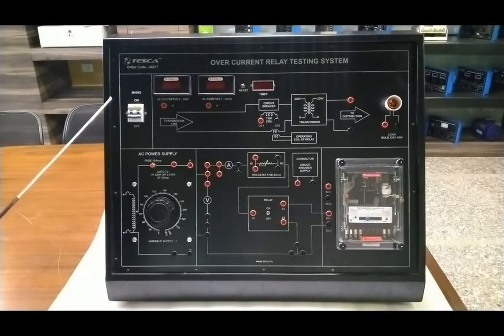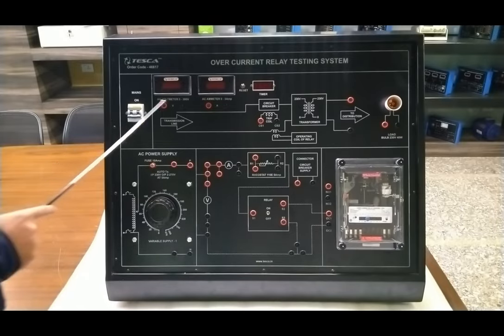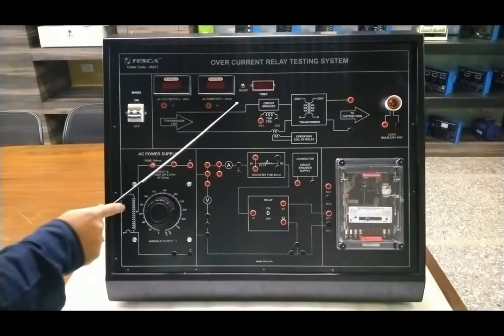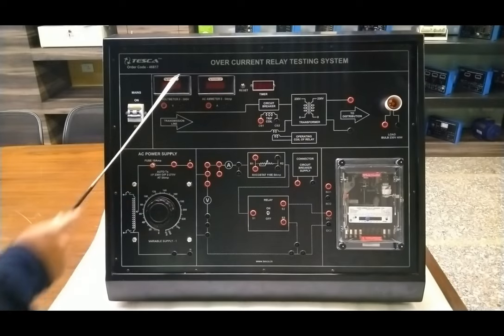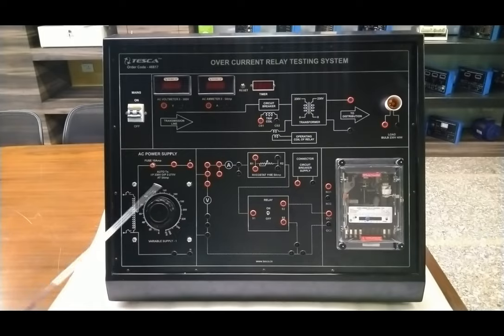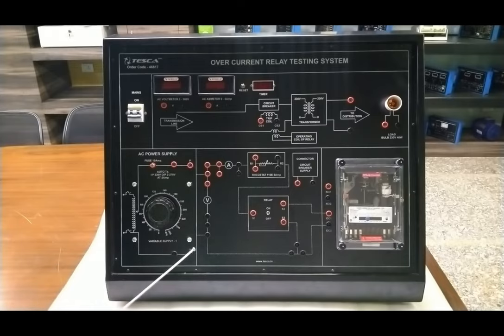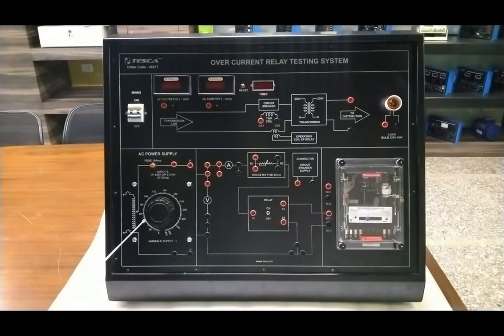You can turn the complete system on and off with the 230 volt power supply. As you turn on the system, the general auxiliary power supply to the meters and timer is provided directly. The supply in the system goes through the variable power supply or variac connected here — this is the auto transformer — and output from 0 to 270 volts in variable form is provided to the complete circuit.